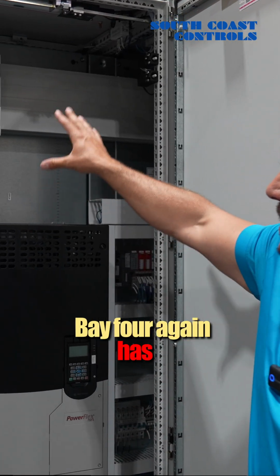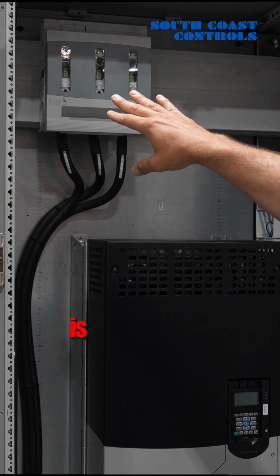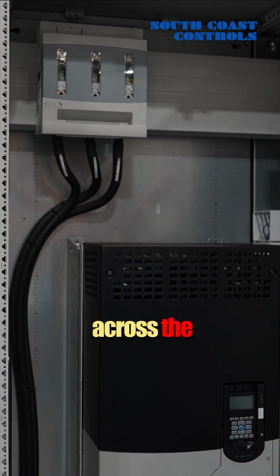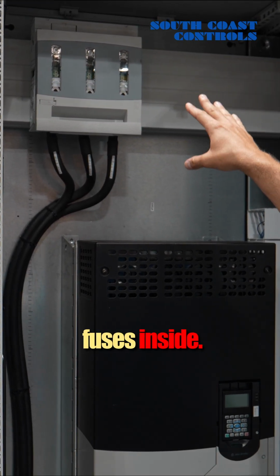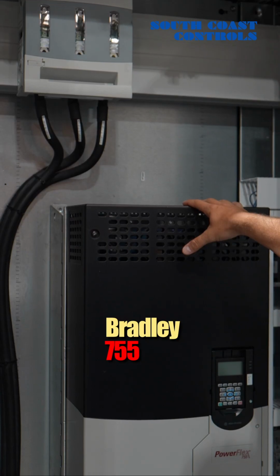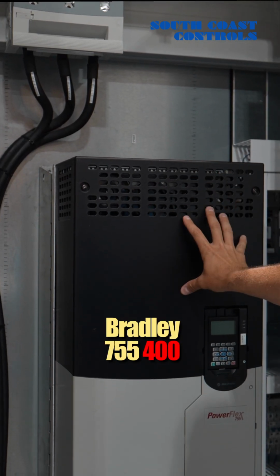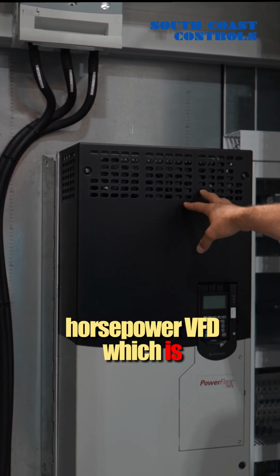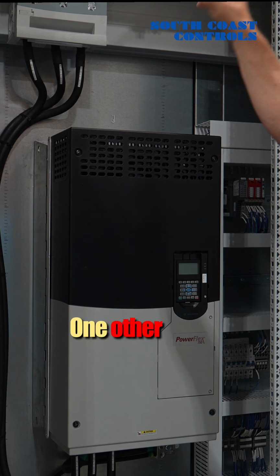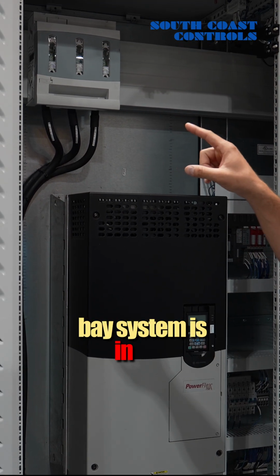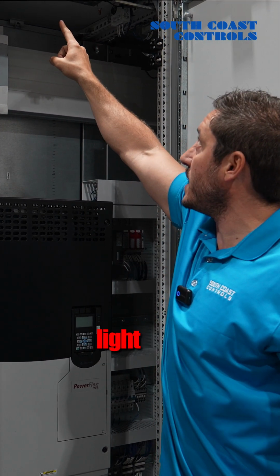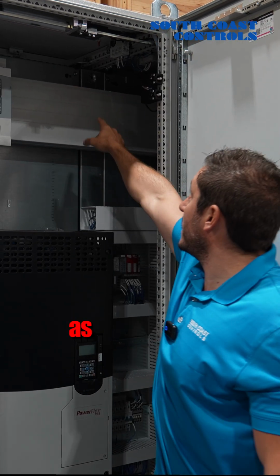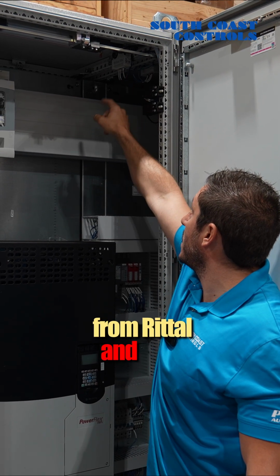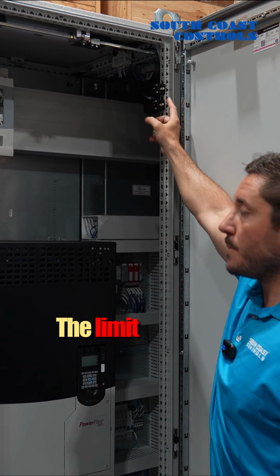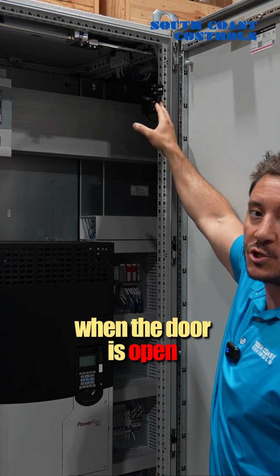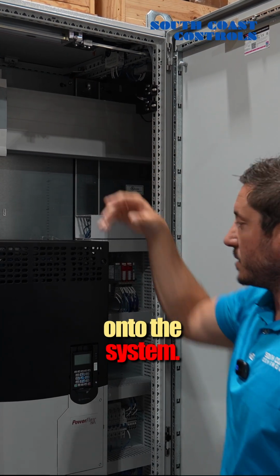Bay 4 again has a Rittal fuse holder that is incorporated onto the busing that goes across the entire structure with little fuses inside. Then we have an Allen Bradley 755 400 horsepower VFD, which is our 3rd VFD in the cabinet. One other thing is each bay system will have a panel mounted light from Rittal as well as thermostats from Rittal and limit switches from Rittal. The limit switches, of course, are used for when the door is open, light will be turned on to the system.